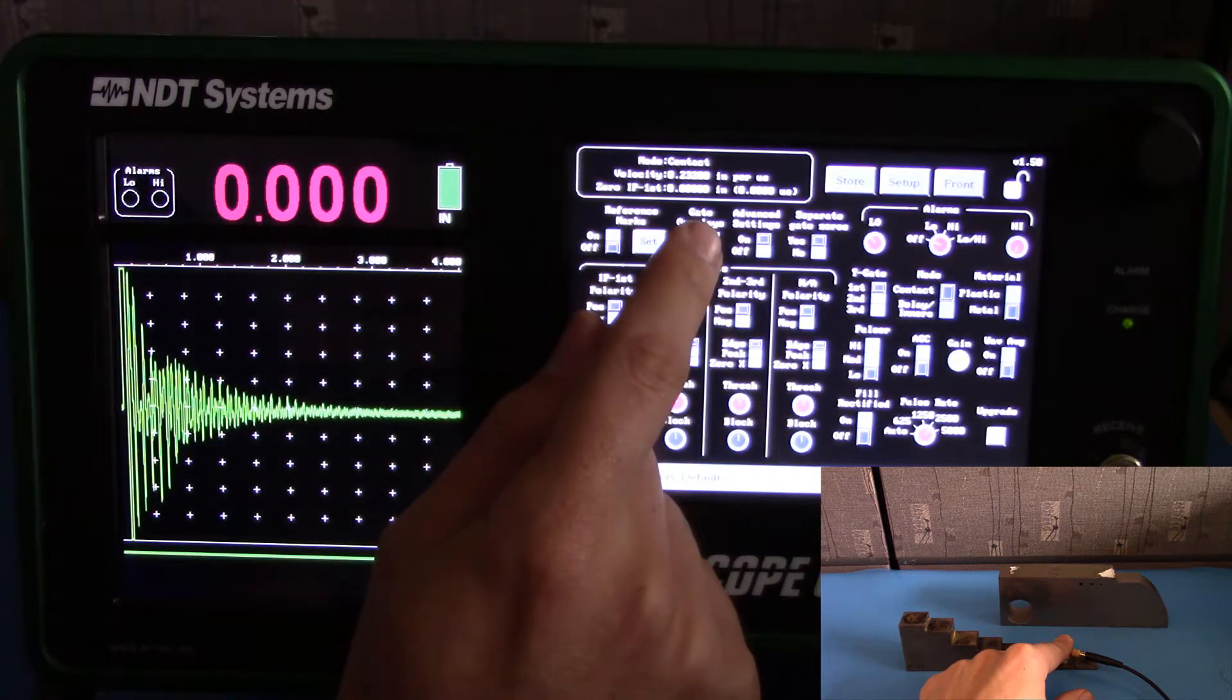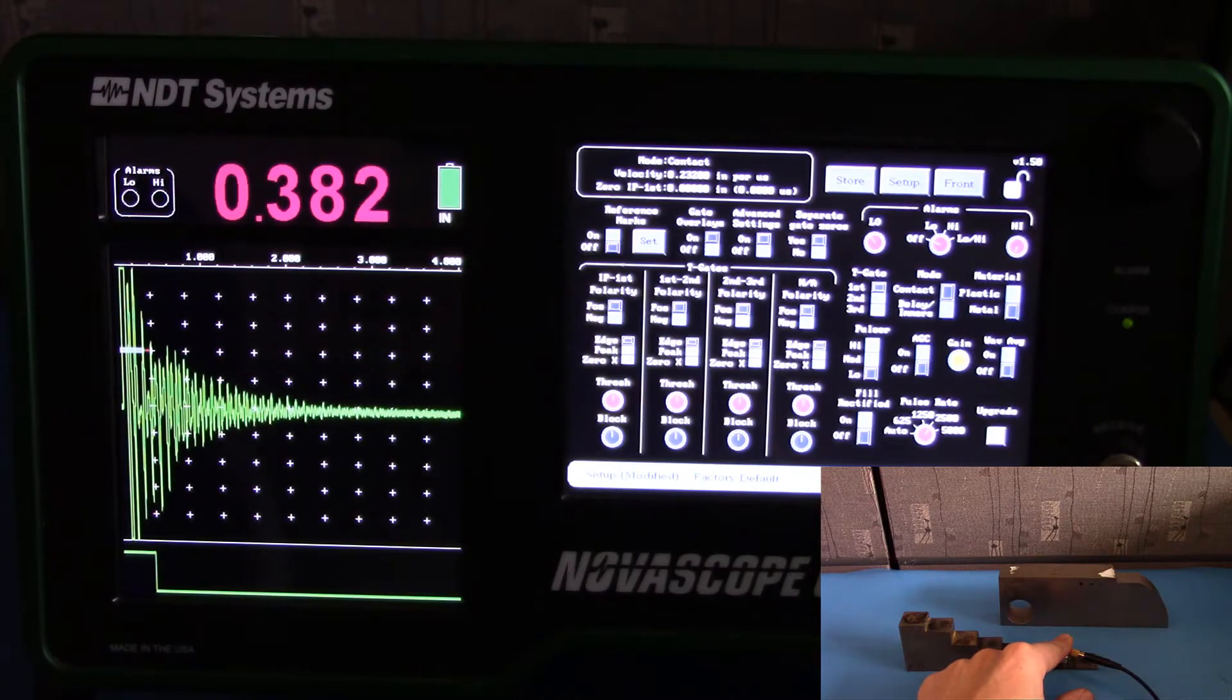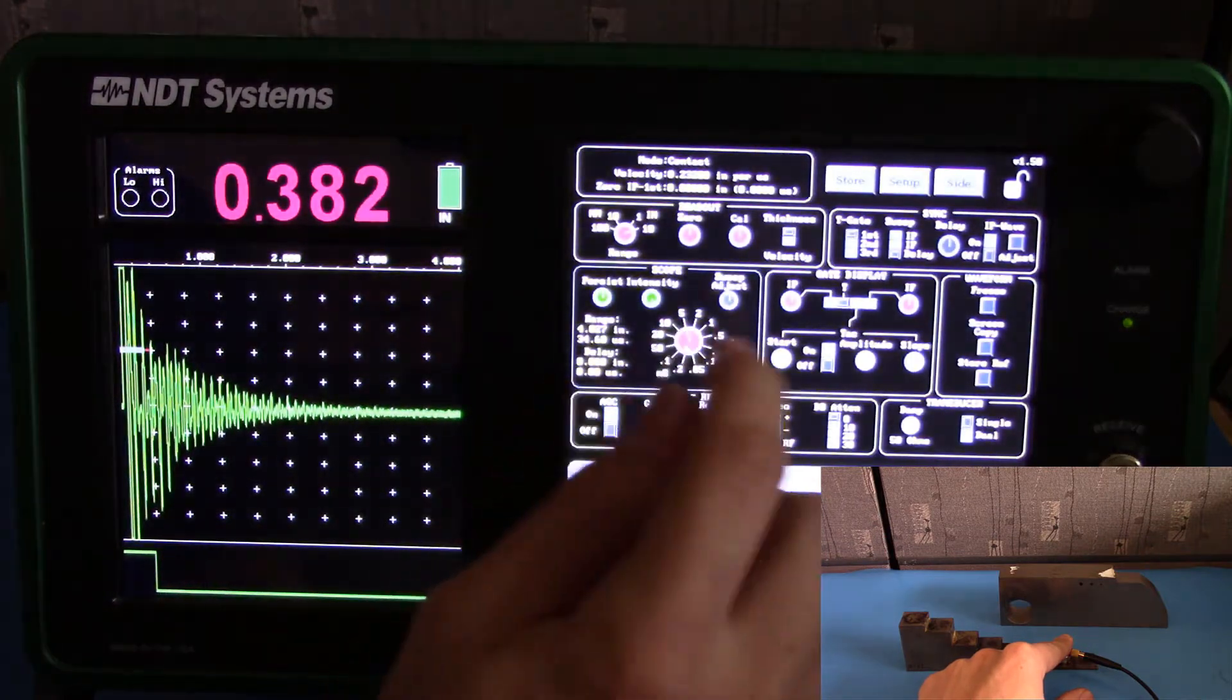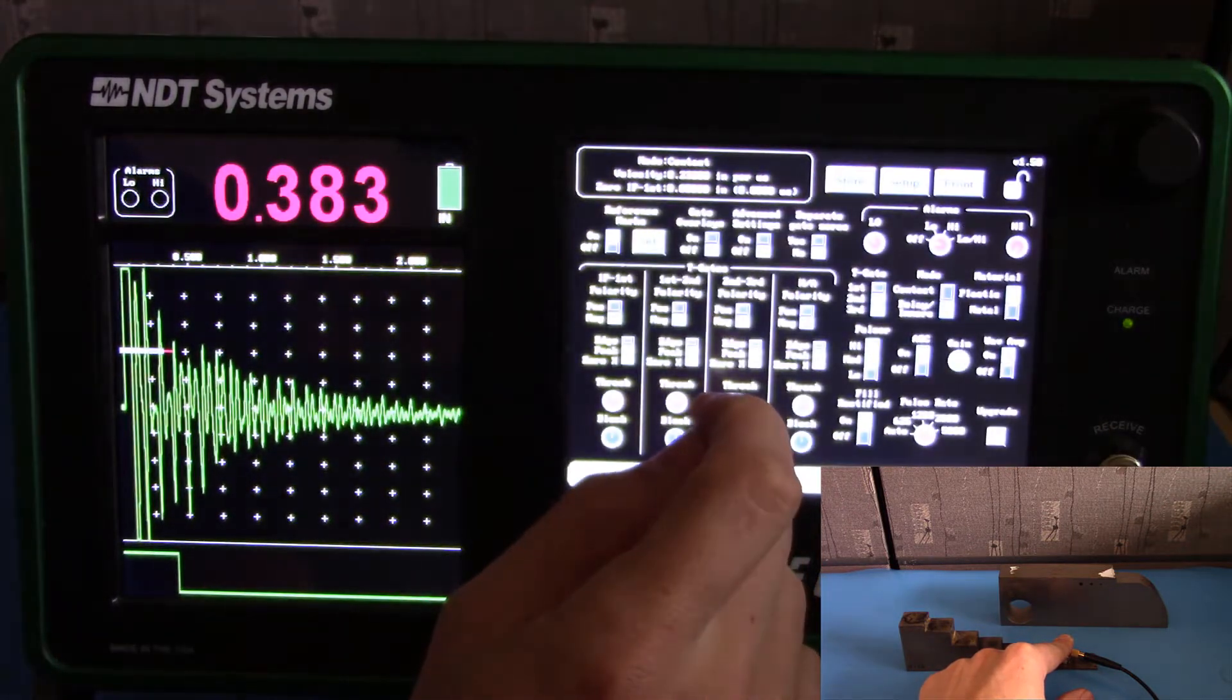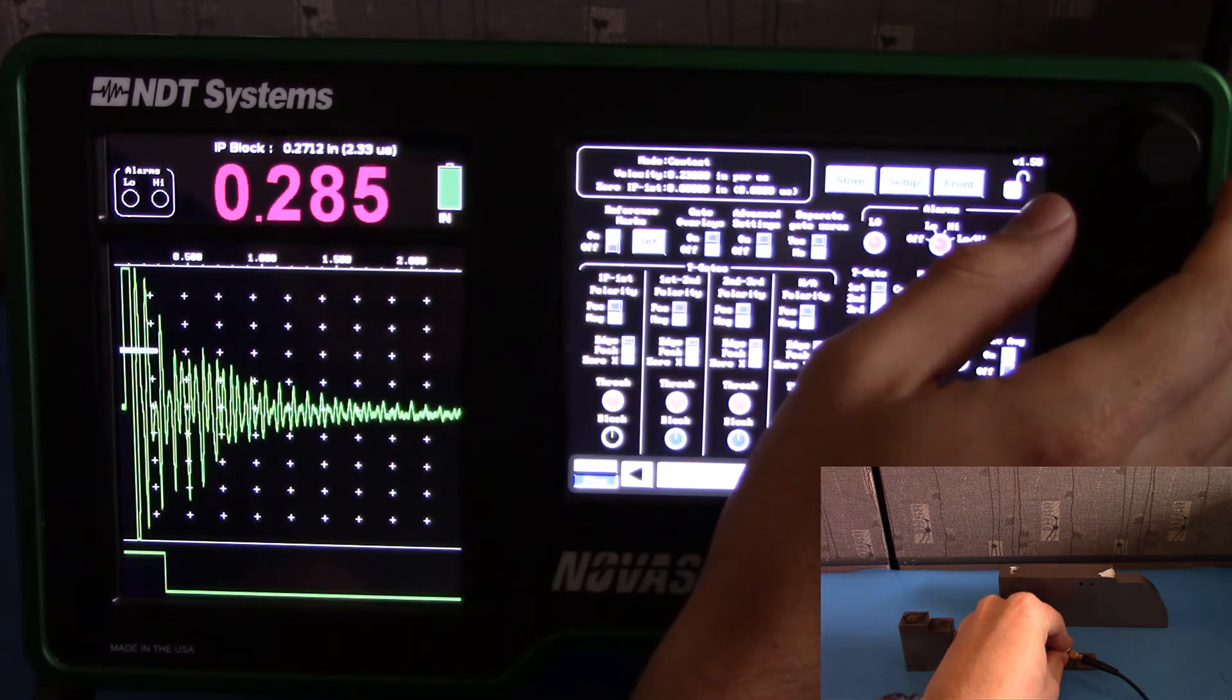Next, while it's coupled, go to the side menu. Go to the Advanced Settings Switch and hit On. Hit Gate Overlays. And now you'll see the trigger gate. We want to set this so that it triggers on the first echo. It should be about right here. Let's go to the front and decrease our range down to 2 inches. Go back to the side. Go to the IP block and decrease that until we hit our first return echo.